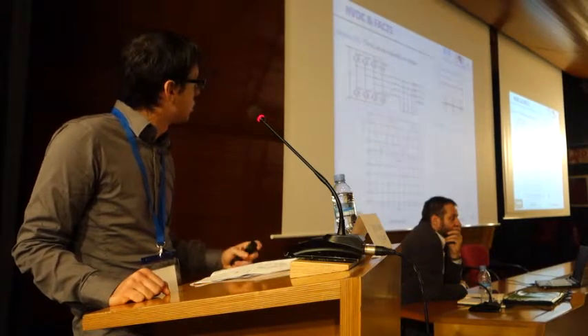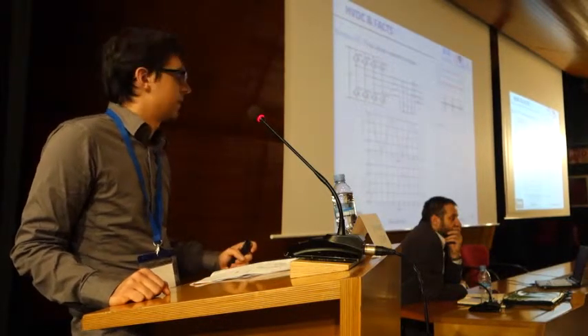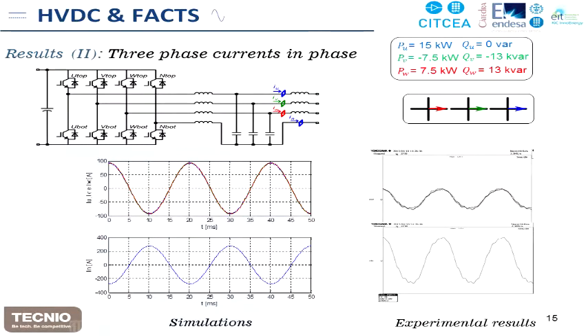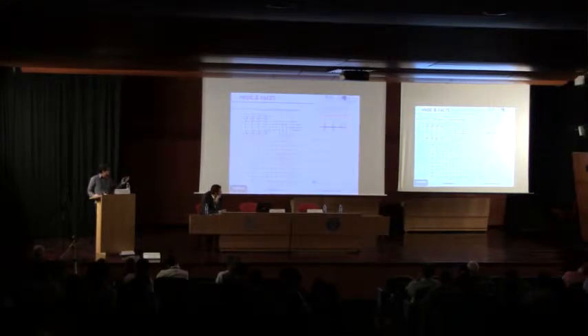We can also show one more extreme scenario where, depending on the reference, we can make the system have the 3 active currents in phase. In this case, we have proposed to reference the system for phase U 15 kilowatts, for phase V minus 7.5 kilowatts and minus 13 kilowatts, and in phase W 7.5 kilowatts and 13 kilowatts. Making these references feasible, it is possible to observe that all the 3 active currents are almost in phase, and this means that all the current will return through the neutral. This is one of the main reasons why we need to triplicate the converter, in this case using the same modules, which implies the control of the neutral wire.